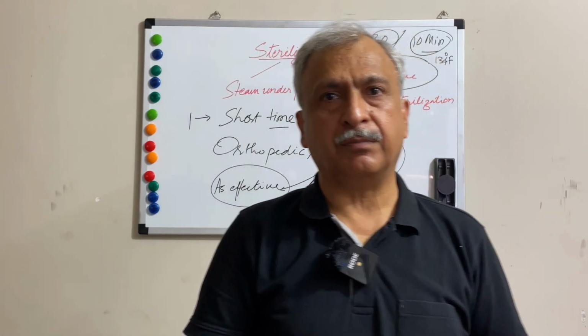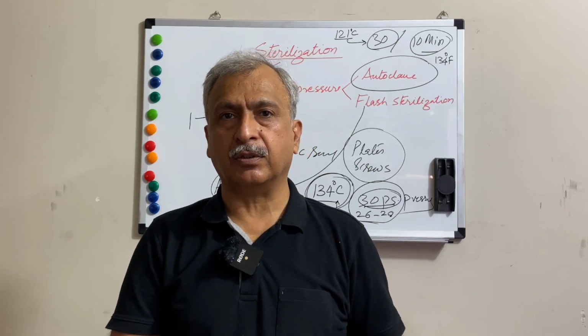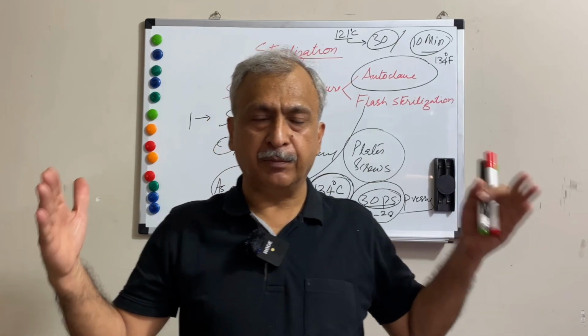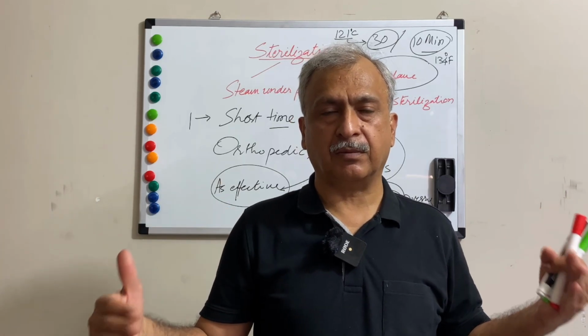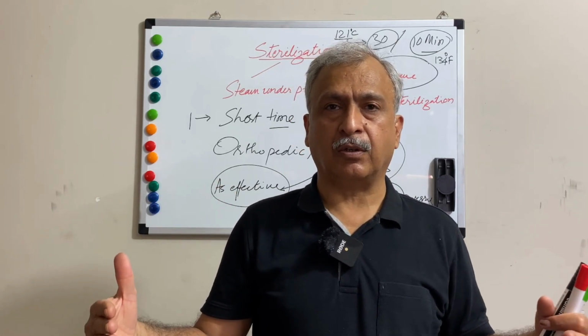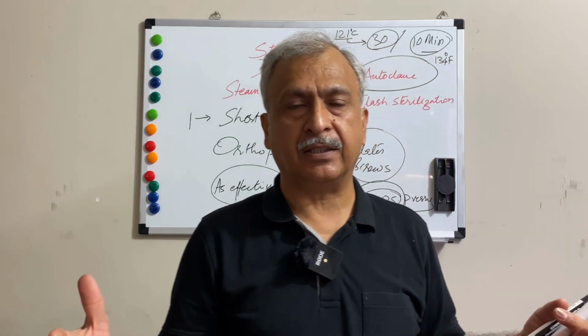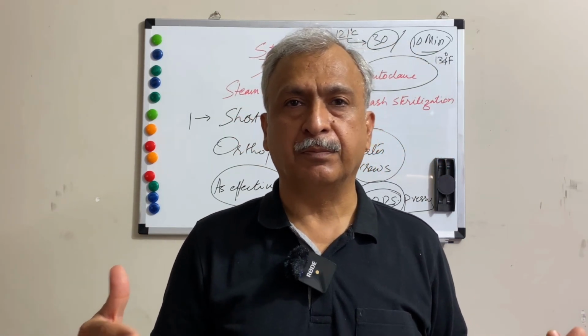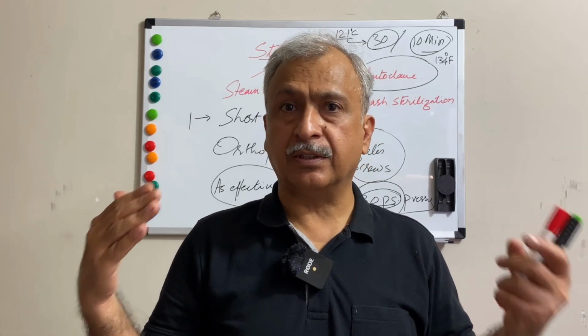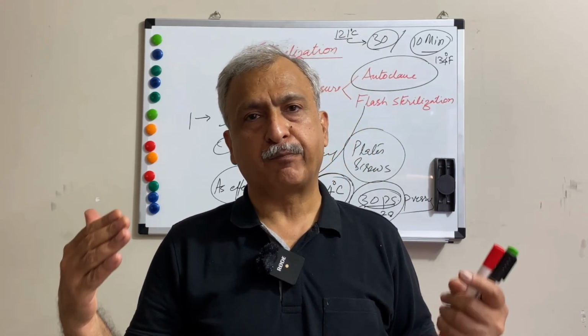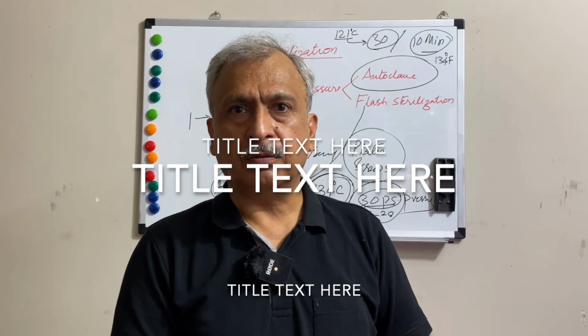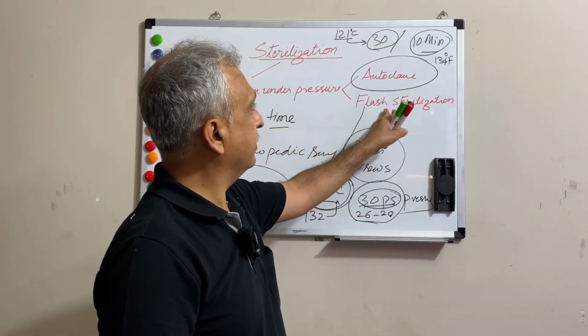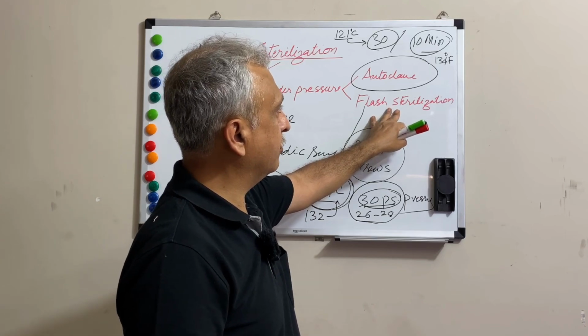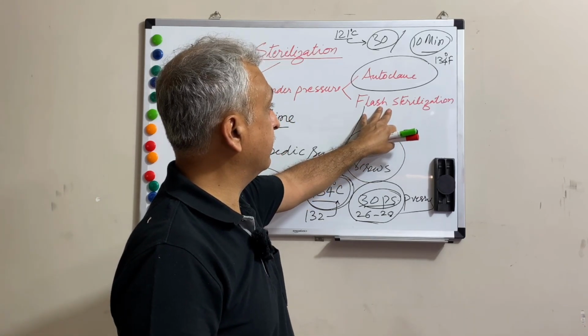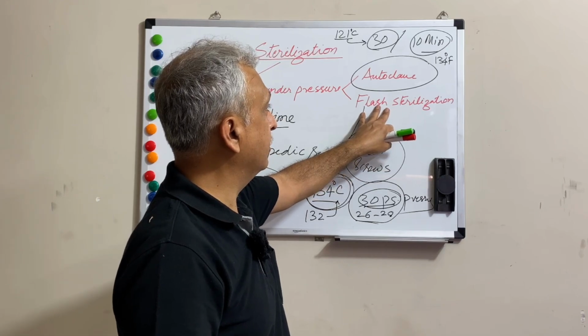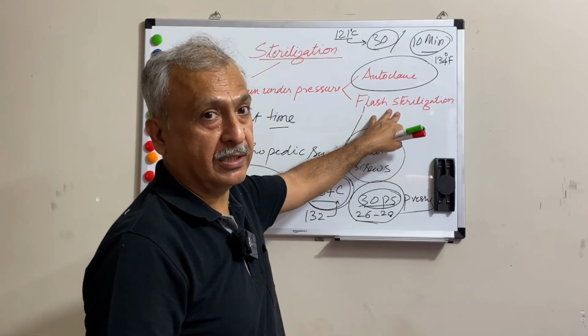So this method should never be your alternative to the normal autoclave. It is used in between surgeries when all of a sudden some requirement occurs, because of a shortage of screws, or a plate that is not fitting into the pre-planned space in orthopedic practice. This method of sterilization is not as effective, and it should always be used as an emergency when you don't have any other option except flash sterilization.